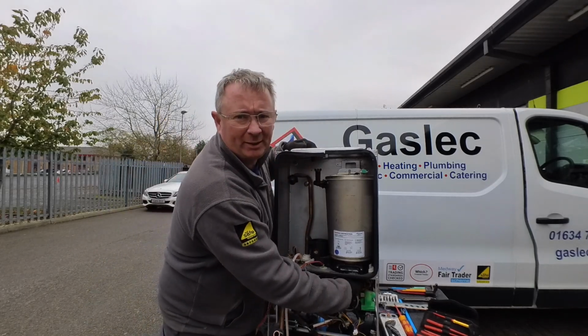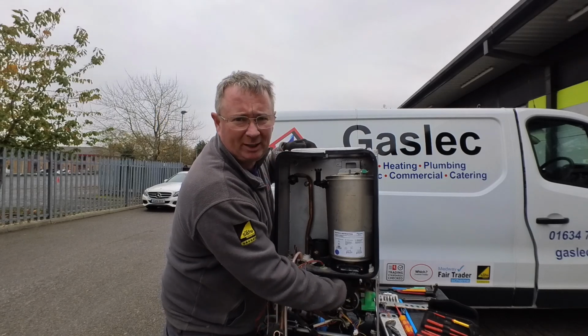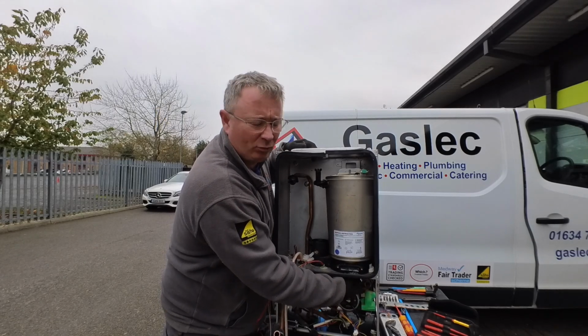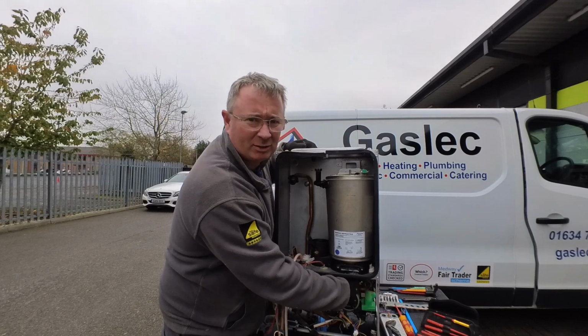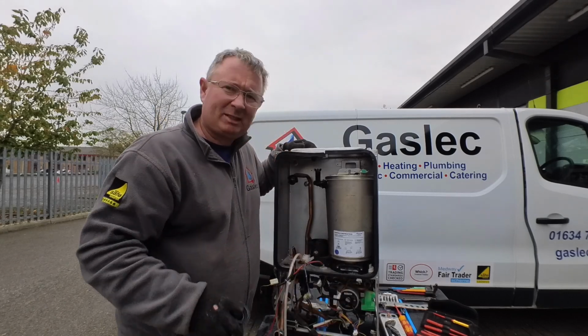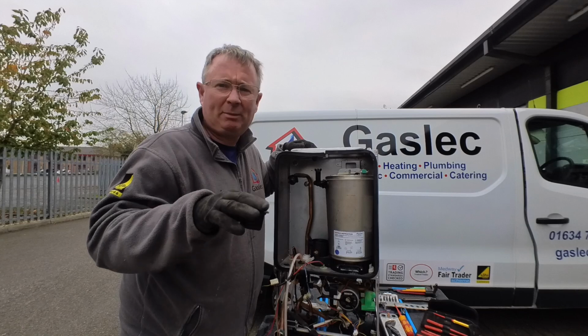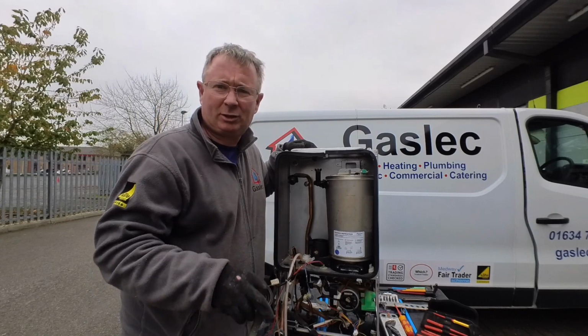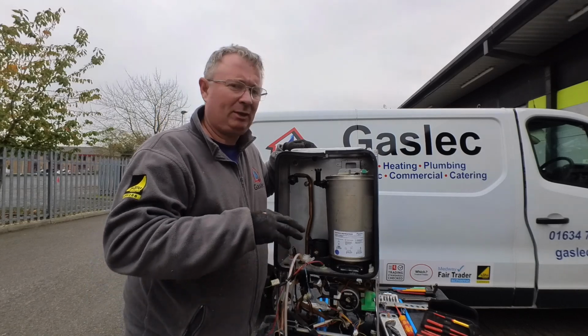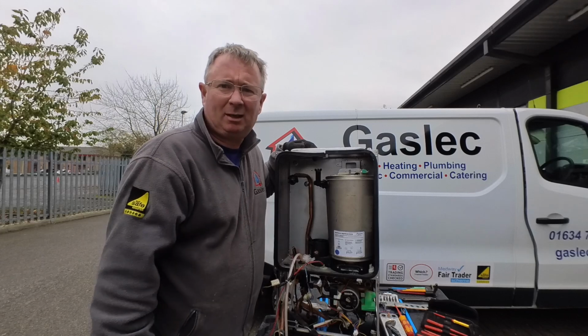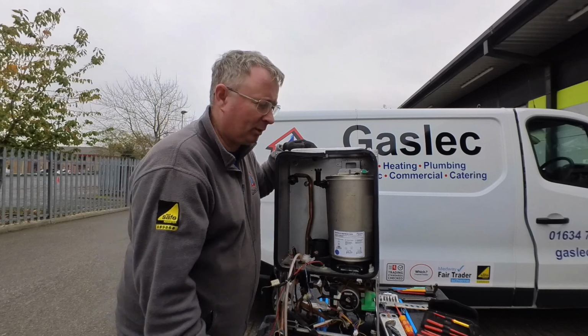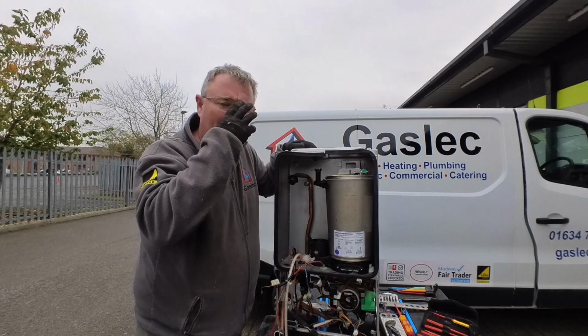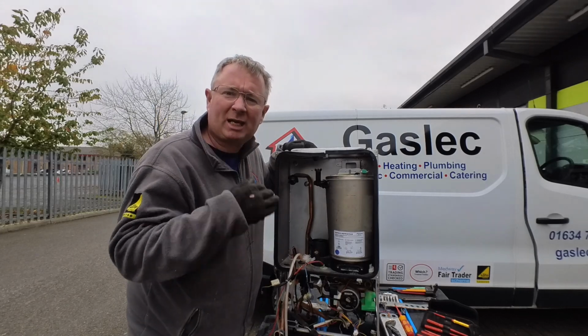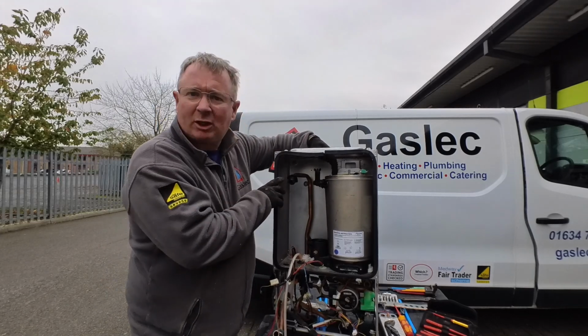We don't do a lot of these because, generally speaking, with the cost of heat exchangers, once you've got a failed one and the boiler's that old, most people will just cut their losses. Once the heat exchanger's gone, you've usually got all the other common faults on these boilers as well, so normally at that point people tend to just tap out financially with it.